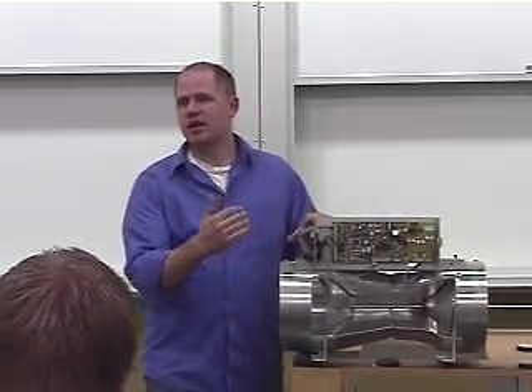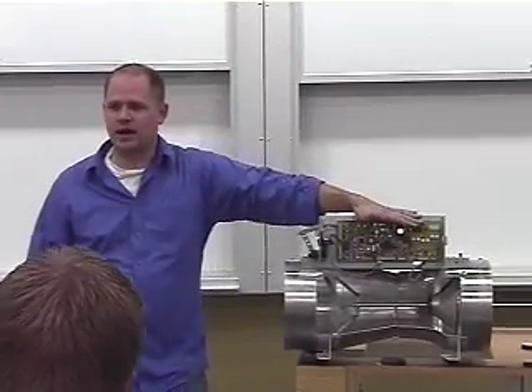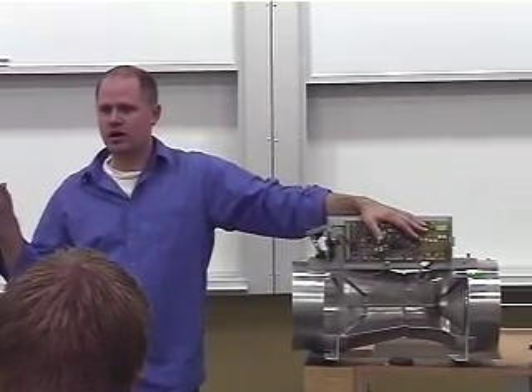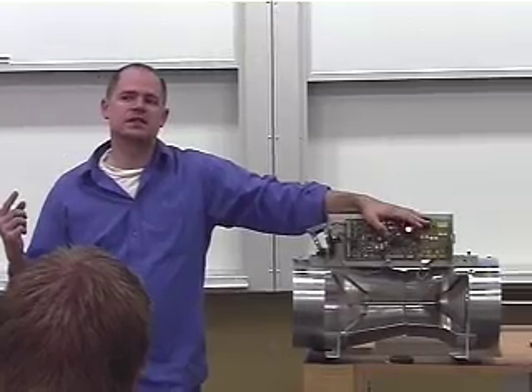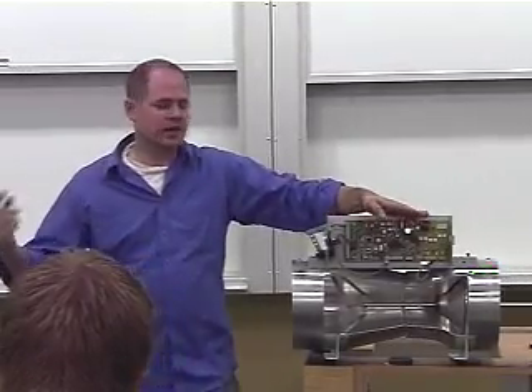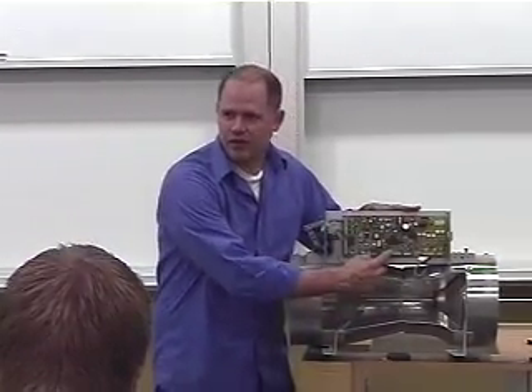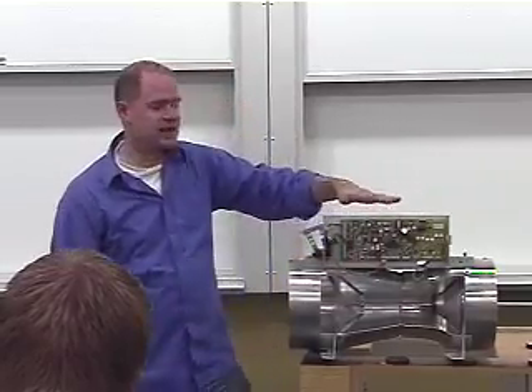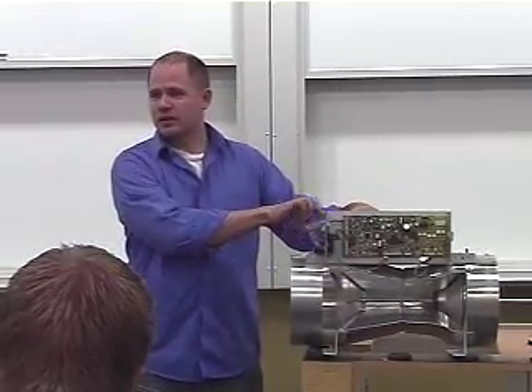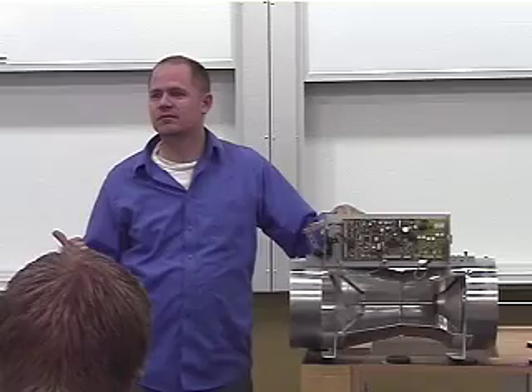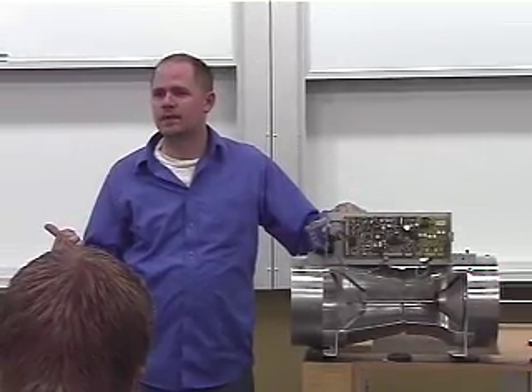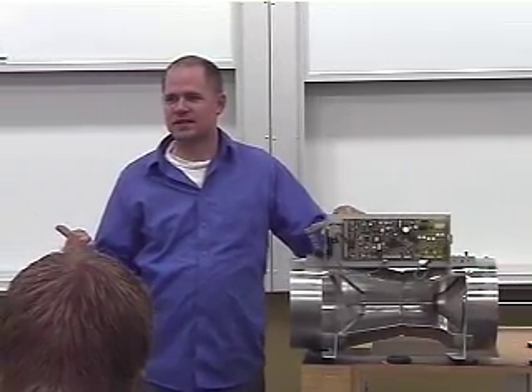And then it stops. The signal from the fume hood monitor up to the Phoenix valve actually is a 0 to 10 volt signal. So it sends a 0 to 10 volt signal into the card on the circuit board. And the card then says, I know where I need to send this motor. So it drives it until it gets there, and then it stops. Does that make sense? Yeah.